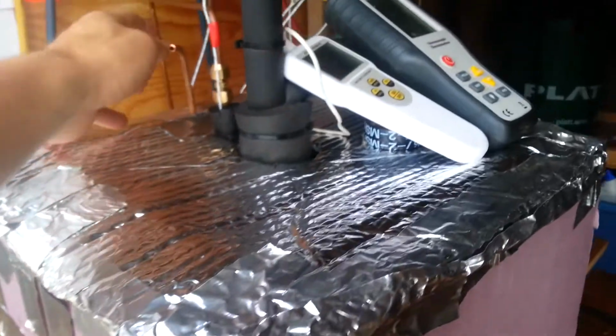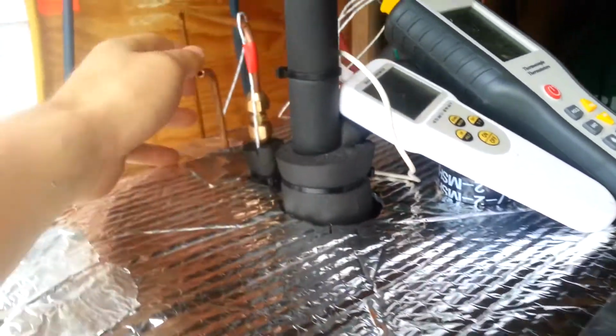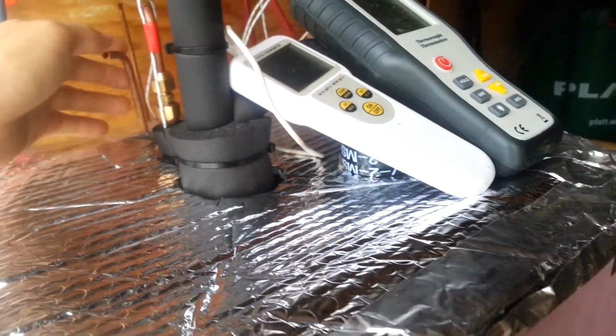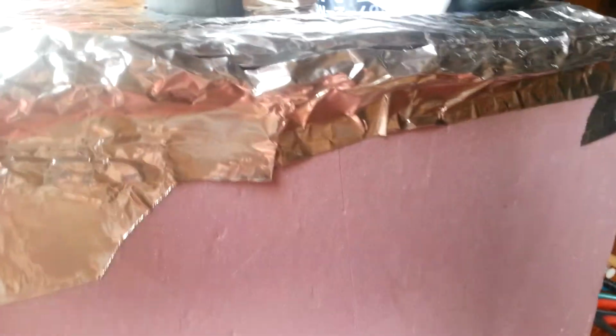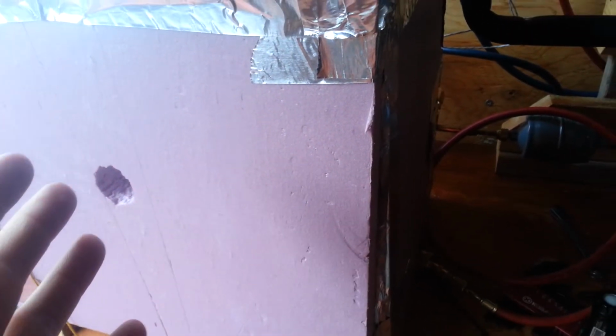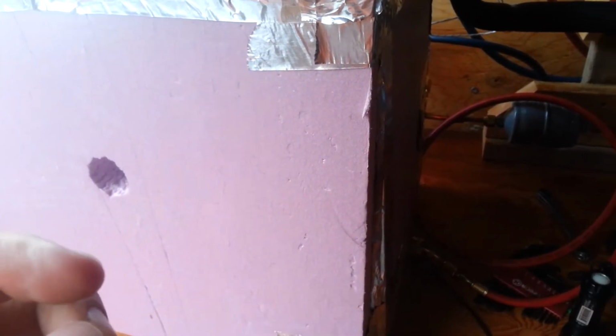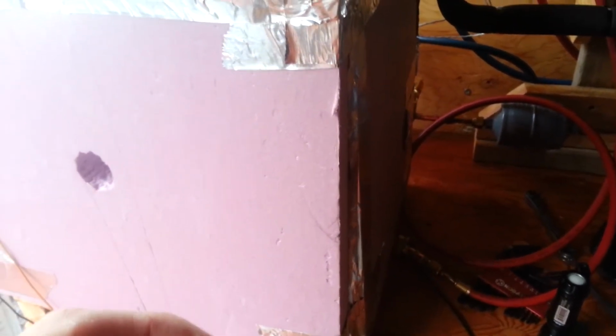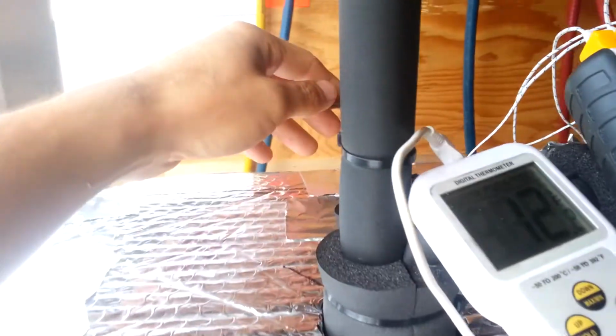And what's cool about this thing is that I don't have any control for superheat. That's not the way this thing is regulated. It's regulated, in some ways, very naturally. It's regulated by the throttle, which I operate myself, but the heat load within the box, the high side pressure, the liquid being admitted to it, and the compressor, all those things together dictate what the temperature of the coil is going to be. But the superheat is almost always going to be, if not dead on to the associated temperature at the suction pressure, just a few degrees higher, no matter where I set this throttle.